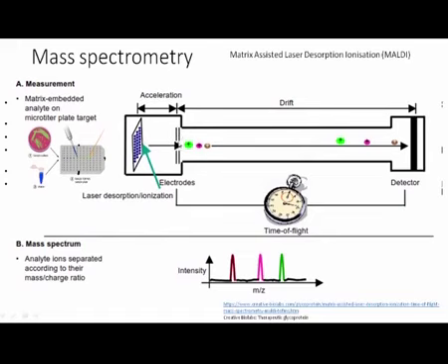These are the electrodes. So, this channel actually pulls all the plume of ions to flow past, because this is kept at a very high voltage. So, they just flow past or move towards these electrodes, and once they move towards these electrodes, there is an orifice at the center of the electrode which allows the ions which are accelerated to pass through this channel, and then depending upon their mass by charge, they will start flowing all the way through this huge flight tube to the end and fall on a detector.